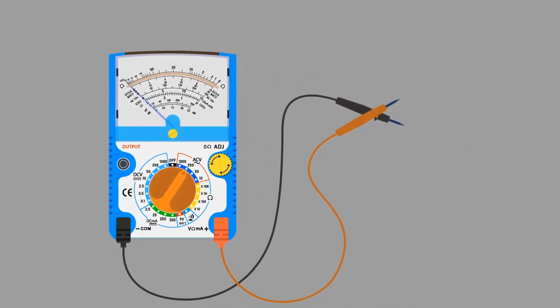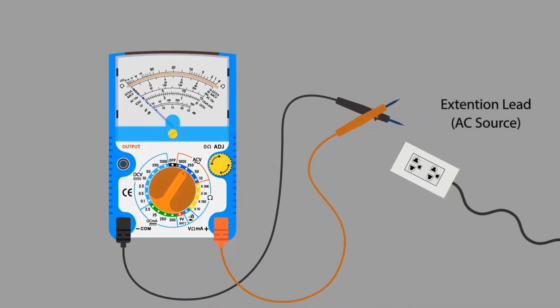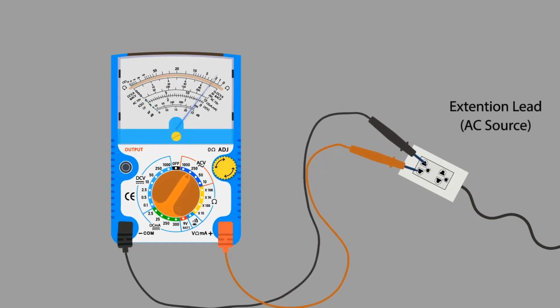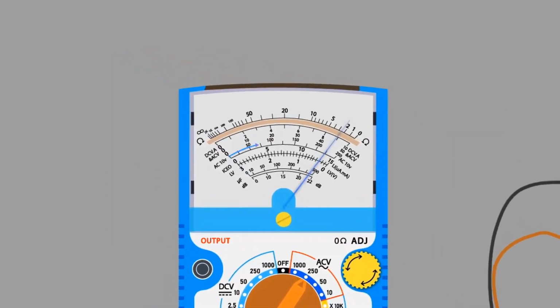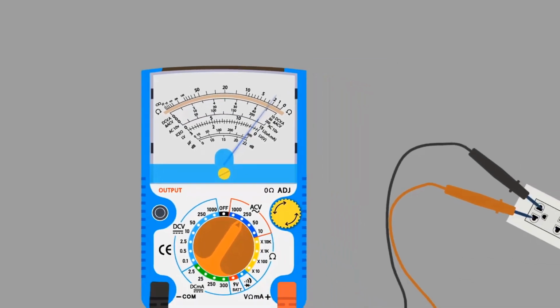And now we'll measure the voltage directly across the mains. That is the voltage we have across all our plug points. And as you can see, the pointer has moved ahead. And because we are taking measurements on the 250 scale, we'll take the readings on the 250 scale, and we can see it is almost around 225 volts, which is correct.